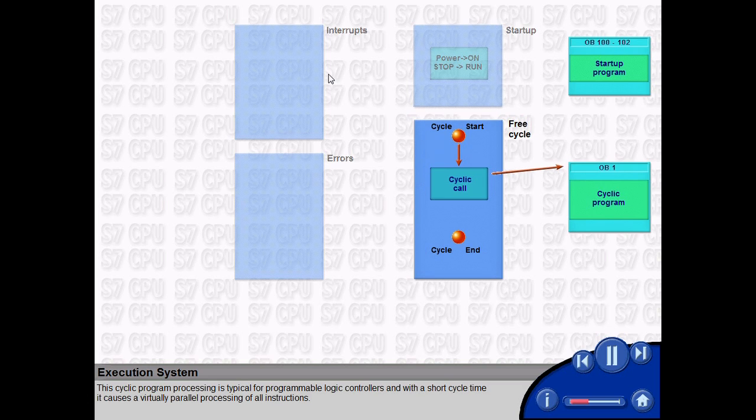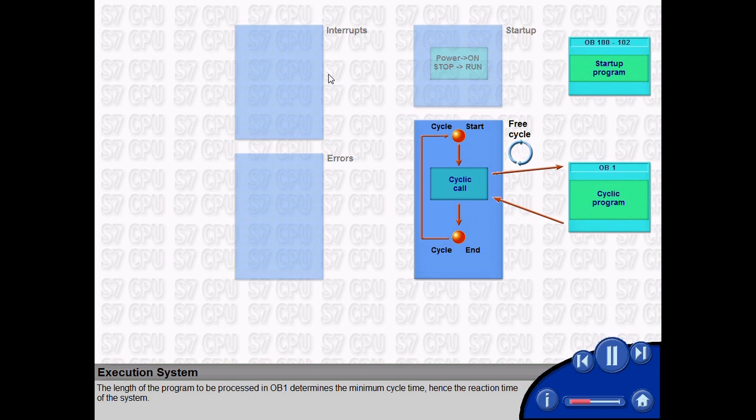This means the main program in OB1 is continuously and cyclically processed. This cyclic program processing is typical for programmable logic controllers. And with a short cycle time, it causes a virtually parallel processing of all instructions. The length of the program to be processed in OB1 determines the minimum cycle time, hence the reaction time of the system.